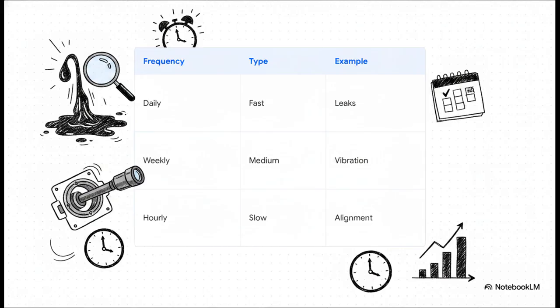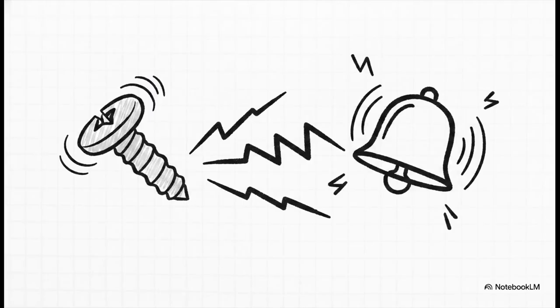Speaking of tracking vibration data, here's a field tip that might just save you a minor heart attack. Getting a high vibration alarm on your monitoring rack isn't automatically a mechanical disaster. Believe it or not, sometimes it's just electrical noise from a slightly loose thumb screw on the front panel of the monitoring module, interrupting the chassis ground. So always check the physical security of your instruments before you assume the turbine bearings are failing.